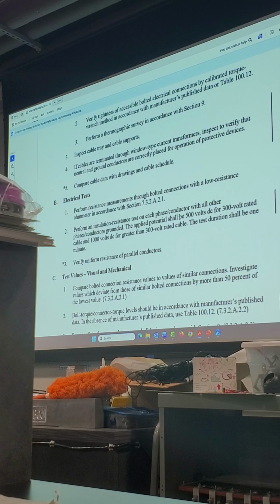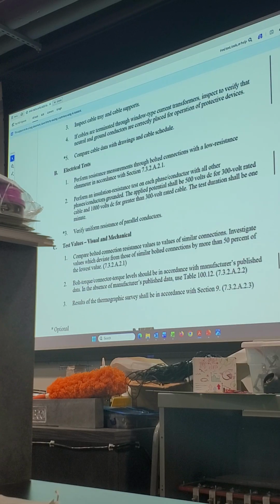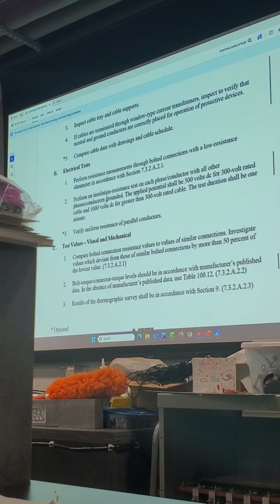Thanks to Irfan hammering at this over the past few weeks - what's this one here? Perform an insulation resistance test on each phase conductor with all other phase conductors grounded. The applied potential shall be 500 volts DC for 300 volt rated cable, and 1000 volts DC for cable rated greater than 300 volts. Test duration shall be 1 minute. Remember, science is both quantifiable and repeatable - we quantify how many volts we subject it to, and it's repeatable at 1 minute.